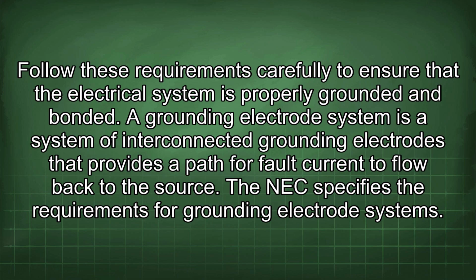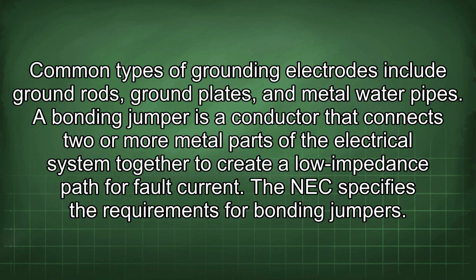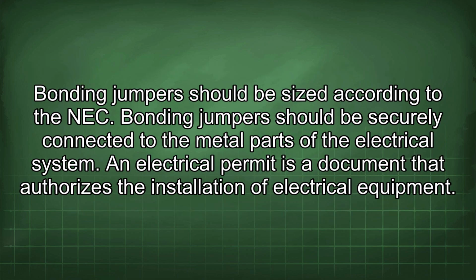A grounding electrode system is a system of interconnected grounding electrodes that provide a path for fault current to flow back to the source. The NEC specifies the requirements for grounding electrode systems. Common types of grounding electrodes include ground rods, ground plates, and metal water pipes. A bonding jumper is a conductor that connects two or more metal parts of the electrical system together to create a low impedance path for fault current. The NEC specifies the requirements for bonding jumpers. Bonding jumpers should be sized according to the NEC. Bonding jumpers should be securely connected to the metal parts of the electrical system.